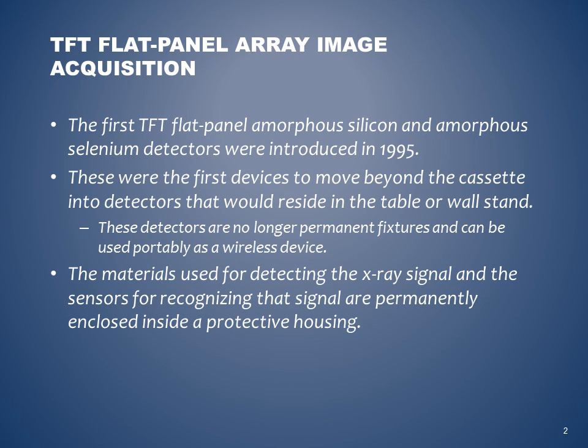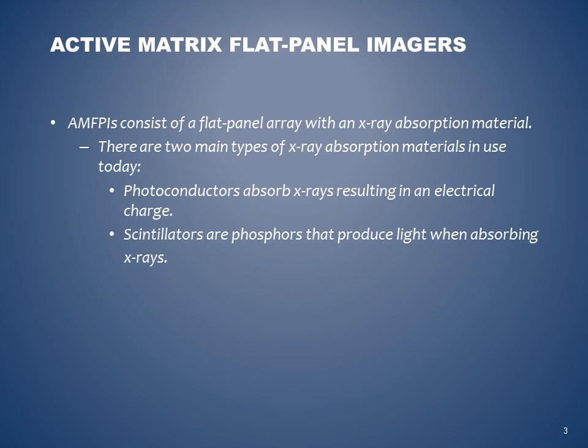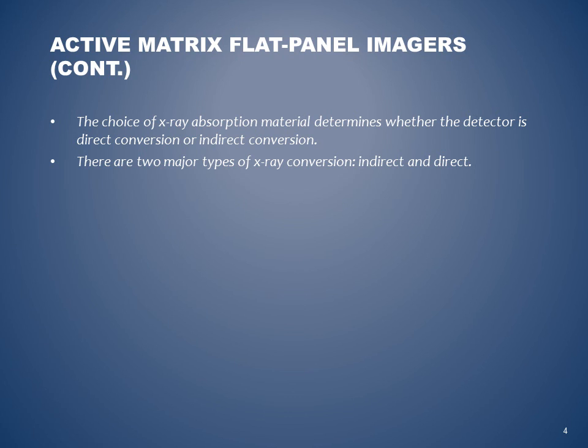The materials used for detecting the X-ray signal and the sensors for recognizing the signal are permanently enclosed inside a protective housing. Active matrix flat panel imagers, AMFPIs, consist of a flat panel array with an X-ray absorption material. There are two main types of X-ray absorption materials in use today: photoconductors, which absorb X-rays, resulting in electronic charge, or scintillators, which are phosphors that produce light when absorbing X-rays. The choice of X-ray absorption material determines whether the detector is direct or indirect conversion. There are two major types of X-ray conversion, which are the indirect and direct.